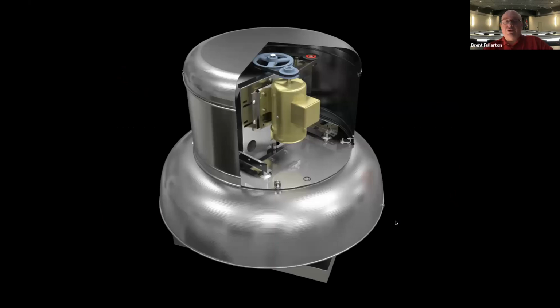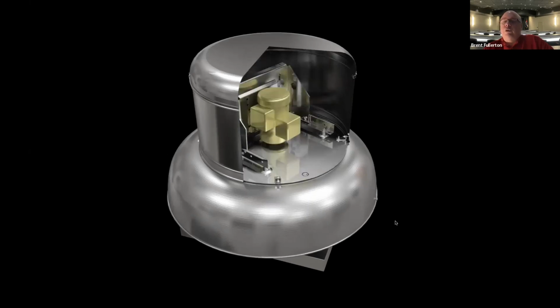First off, belt drive versus direct drive. There are pros and cons of each. Neither one is mutually exclusive. One can be better than the other based upon the way that they're installed, access to that, or also the service crew, the owner, the facility maintenance. So a belt drive, of course, has a motor, belts, and sheaves, that method of transferring the energy from the motor to the fan shaft, whereas a direct drive has the motor coupled directly to the rotating device.